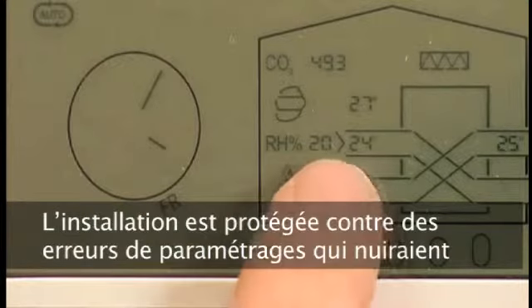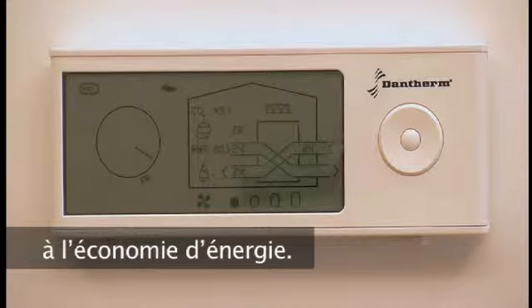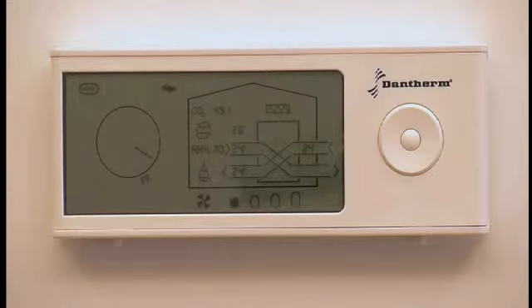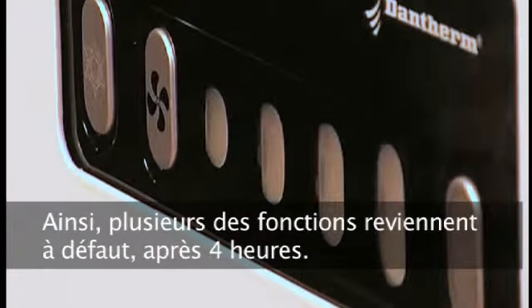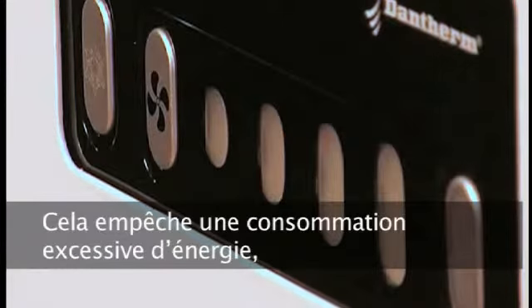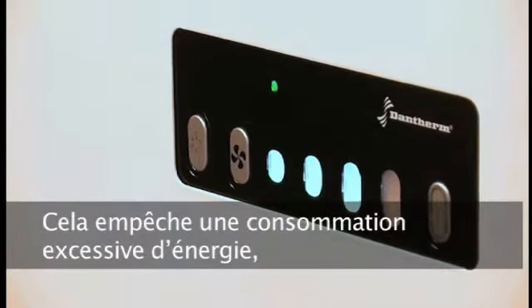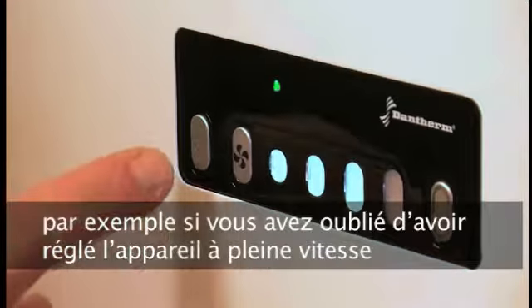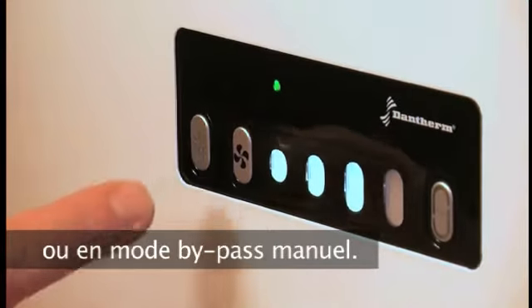The installation is always secured against incorrect and uneconomical operation over a longer period. Thus, more of the functions turn back to default settings after 4 hours. This prevents inconvenient, excessive energy consumption, if, for example, you forget that you have set the unit to full speed or manual bypass.